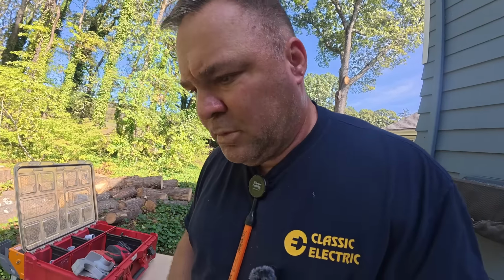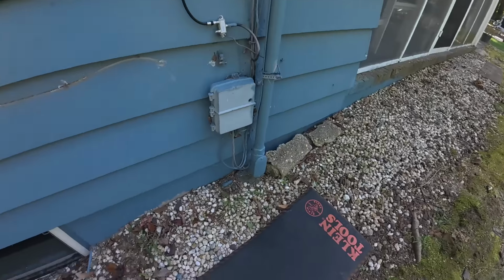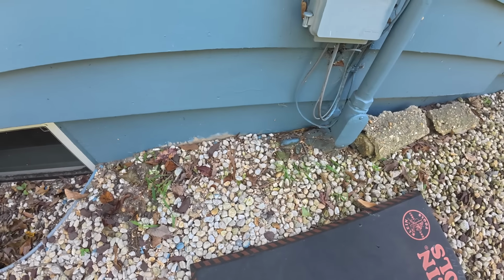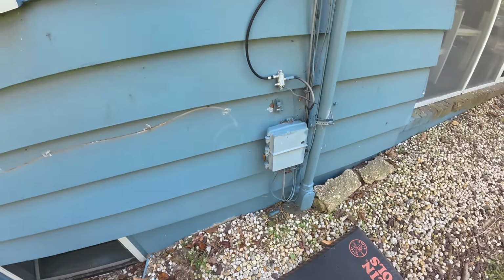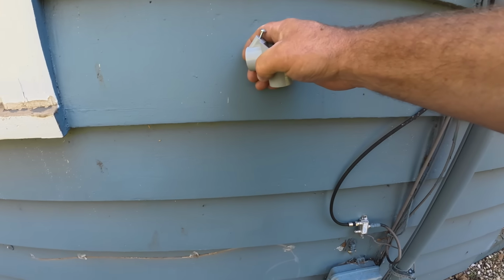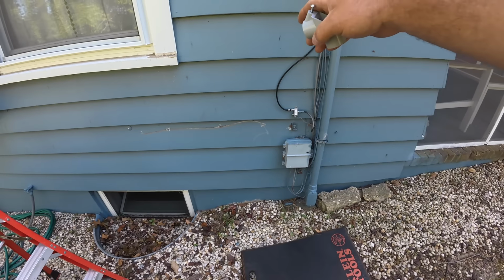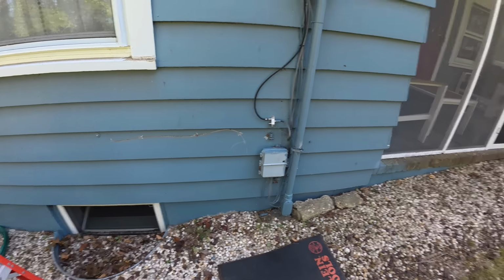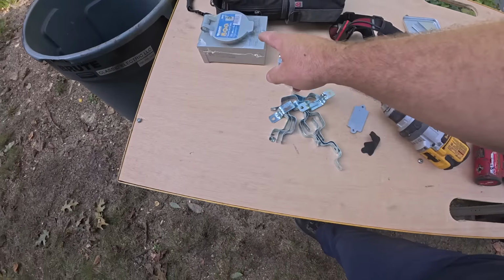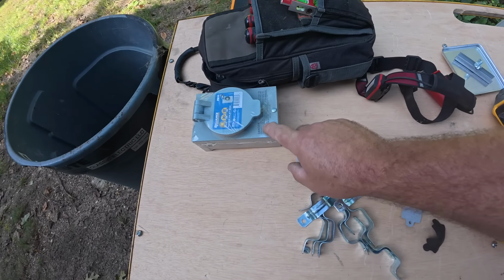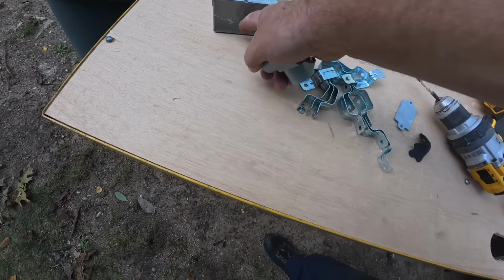So I'm getting ready to install the inlet box for the portable generator wiring, and because the only way into the basement is down so low, it doesn't make any sense to put the inlet down there. What we want to do is put the inlet somewhere up here, maybe like 4 feet above the ground. This way, when there's an emergency, it might be 3 feet of snow, it might be 4 feet of snow, we don't want to have the inlet box in the snow, so that's why we're going to come into the bottom with some PVC.